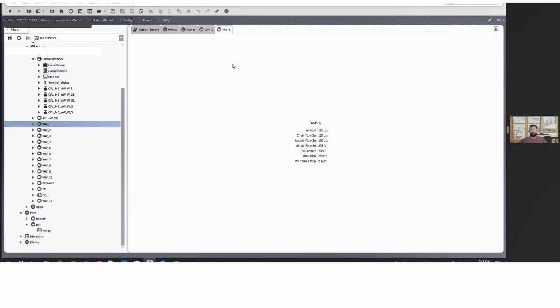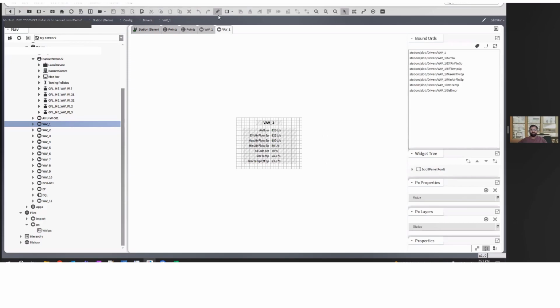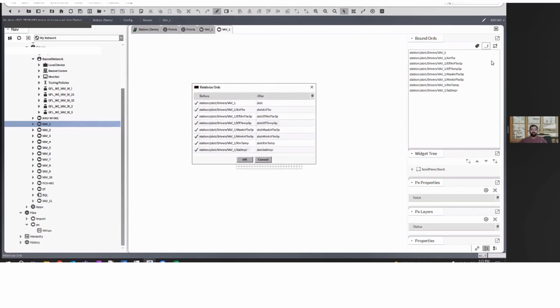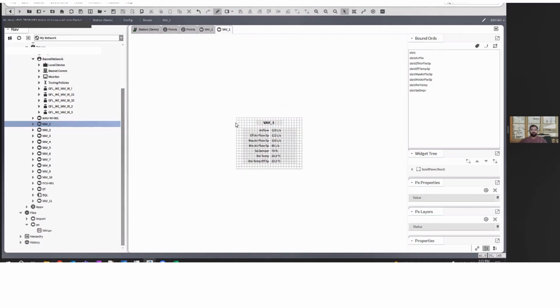The only thing you need to do is edit the PX, and there's a small button in the bound ords called relativize ords. If you click it, it relativizes the name and removes the common path. So station slot colon driver underscore VAV1 has changed to slot, and station slot colon driver VAV1 underscore airflow has changed to slot colon airflow. It has removed the common path considering all the ords we've bound here. Once I hit OK...